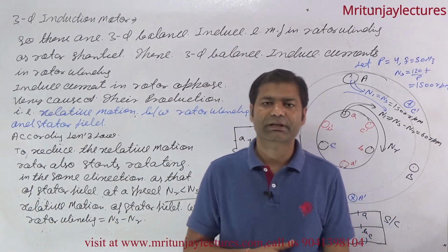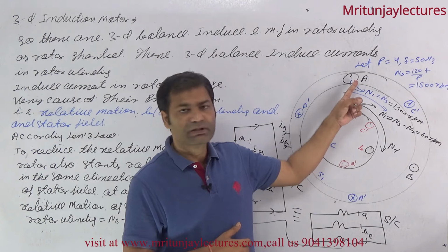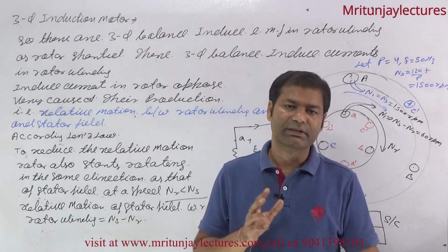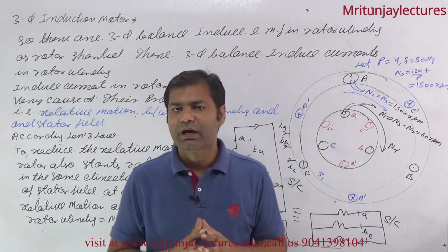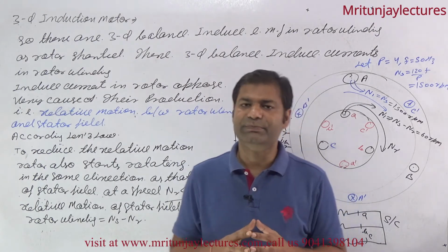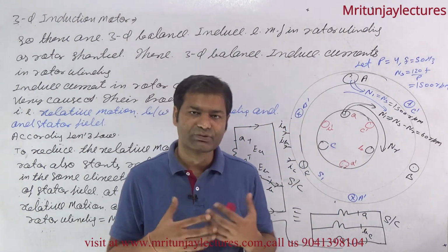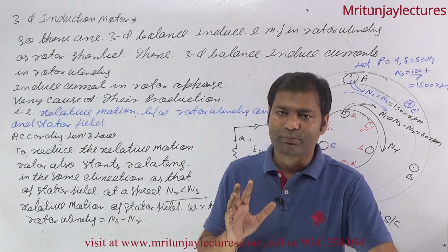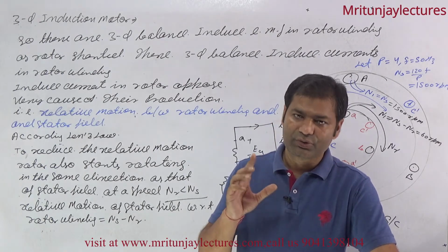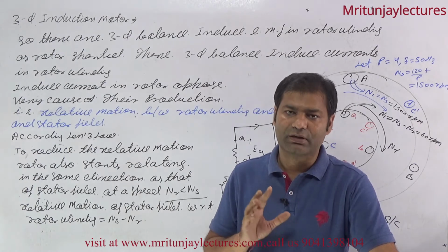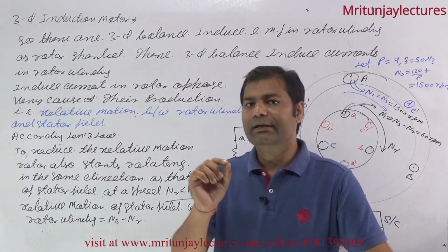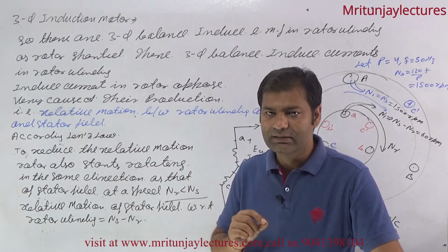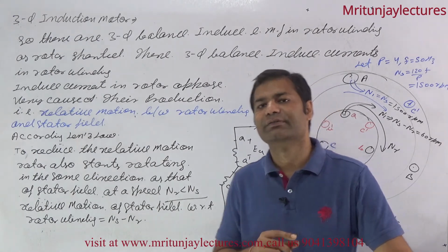The rotor is short circuited. Now relative speed occurs between the stator field and the conductor, so EMF is induced in the rotor winding. The rotor is also a three-phase balanced winding and is short circuited onto itself, so three-phase balanced induced currents are generated in the rotor winding, and the rotor starts rotating in the direction of the field.